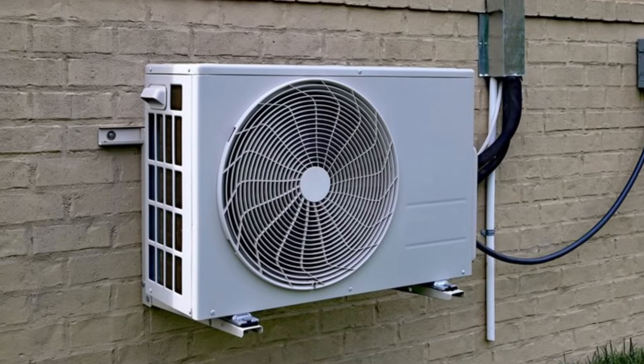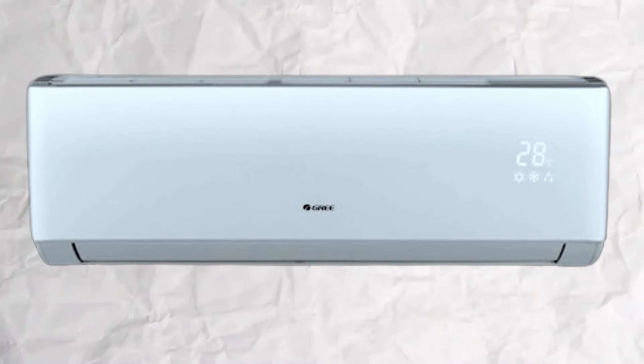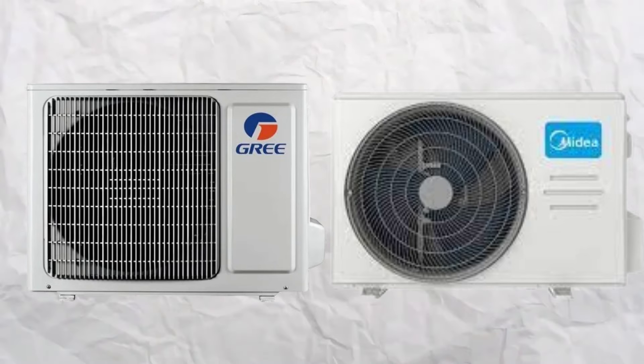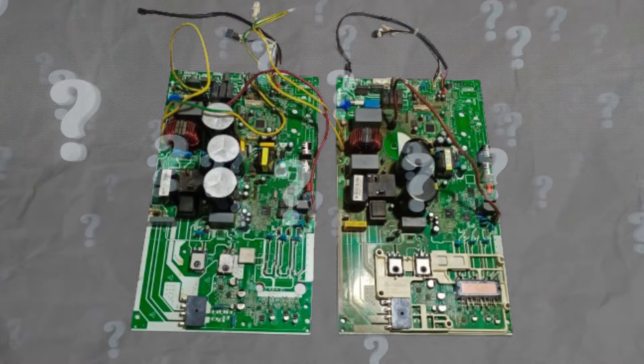This outdoor circuit board of a mini-split air conditioner has arrived for repair, from the GREE company for a 2-ton unit. The indoor unit was showing an E6 error code. I want to tell you about two different brands of air conditioners that have the same circuit board — whether it is possible that both those identical circuit boards could be used with one another.